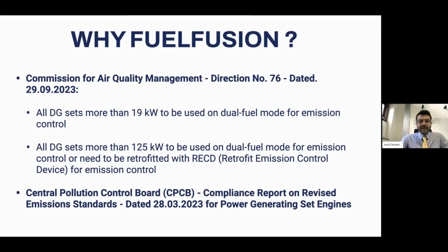Specifically from the Indian context, there was a Commission for Air Quality Management, also called CAQM, which gave a direction number 76, dated September 2023. In that direction document, all DG sets having more than 19 kilowatt capacity have to be used on dual fuel mode so that emissions can be reduced. And all DG sets more than 125 kilowatt need to be used on dual fuel mode or with a retrofitted RECD so that emissions can be reduced.